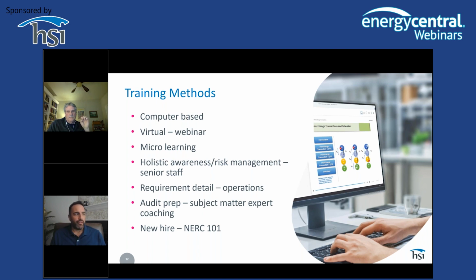that they have. Or for example, say they had a request from a TOP that they had a fault on the line and your device performed as intended. Well, they're going to want to know, for example, digital fault recordings. They're going to want to have that provided or at least made available to them. Your personnel will know to just not erase those records or just maintain those. Usually that is automated, but it's a matter of importance to make sure that they're aware of one example of that, or where to find your relay, your system protection commissioning reports, that sort of thing.